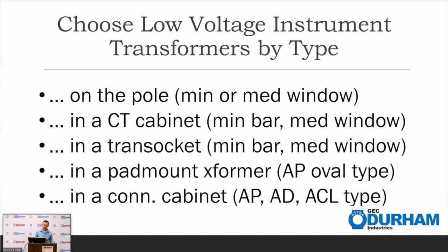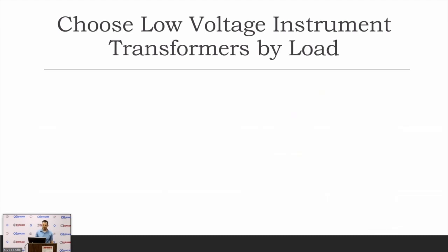And then a secondary connection cabinet. You can use some of those large AD or ACL types in the secondary connection cabinet. But let's just be clear, though, a CT is a CT. So if you're in a pinch and you've got a current transformer with a hole in the middle, you can essentially use it at least in the short term for whatever you need it for.